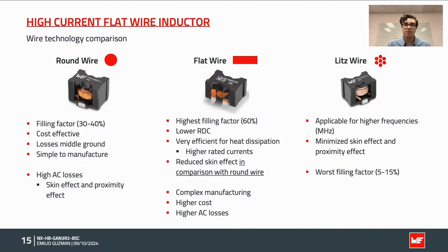For the flat wire, it has the highest filling factor of up to 60%. It has the lower RDC. It is very efficient for heat dissipation with higher rated currents. And it has reduced the skin effect in comparison with the round wire specifically. Now, the flat wire is more complex to manufacture, and thus it increases the cost. And it also has higher AC losses in comparison to the litz wire.